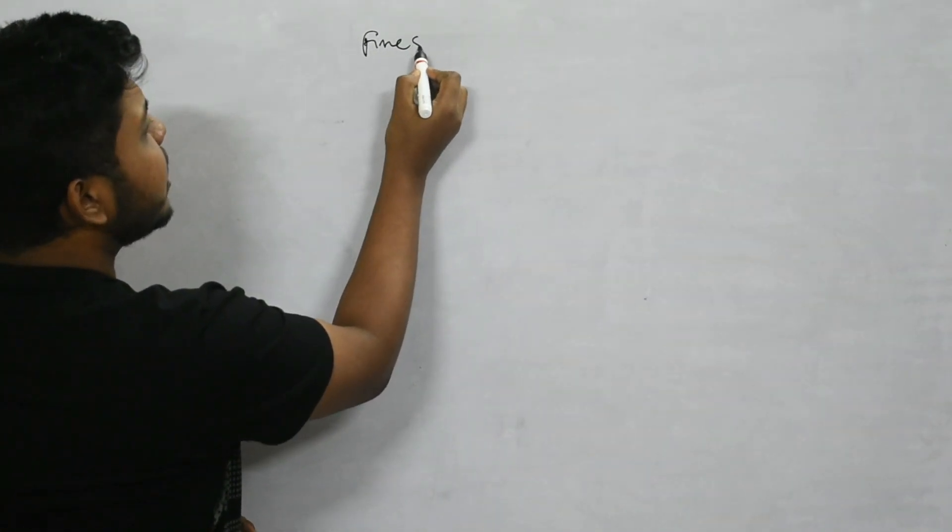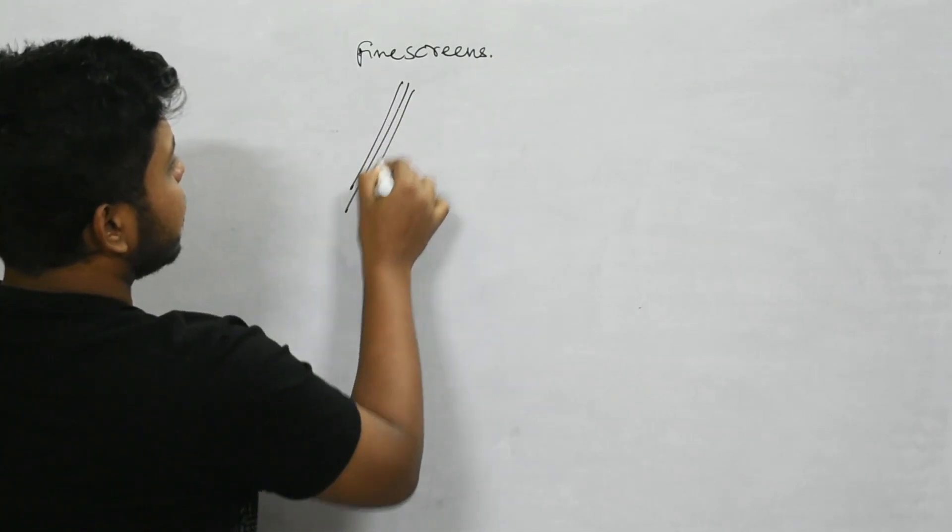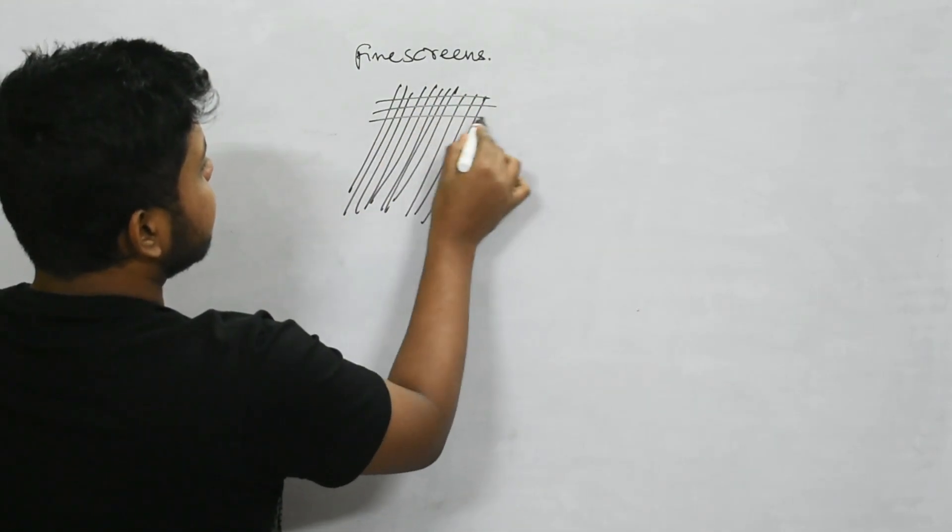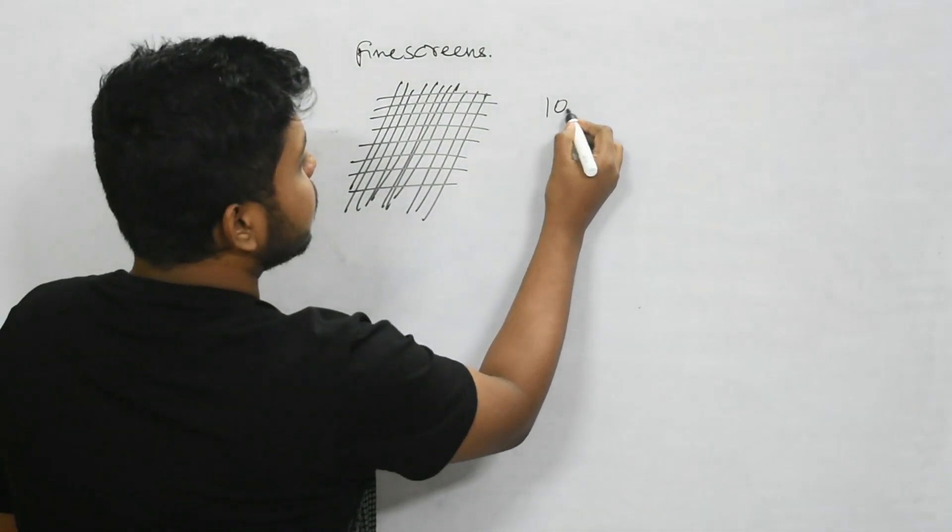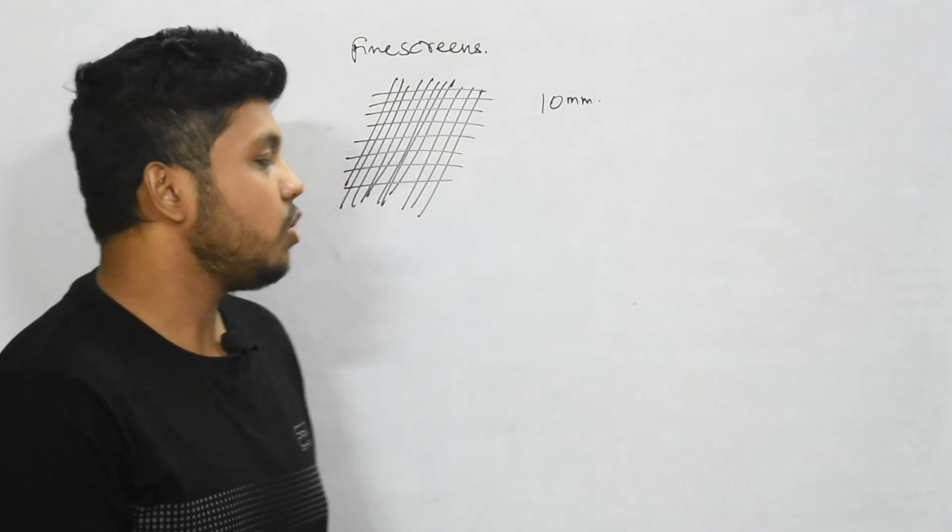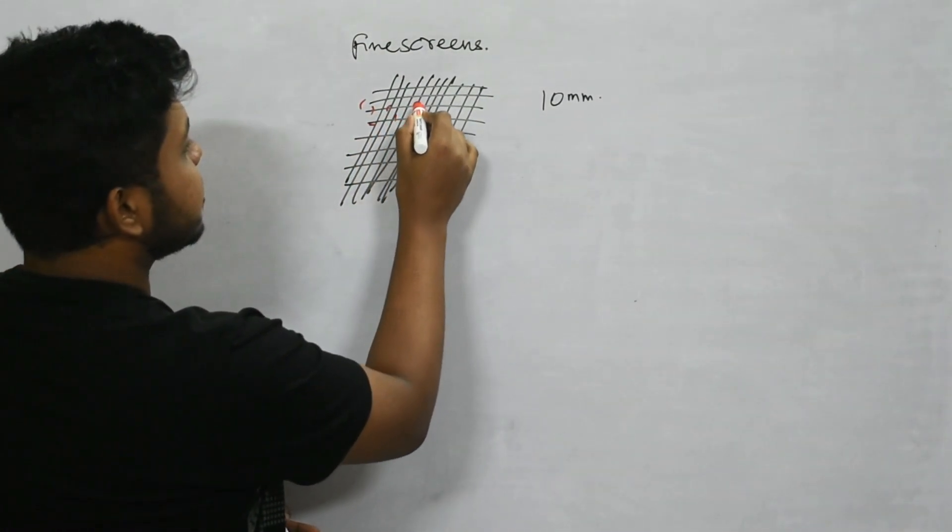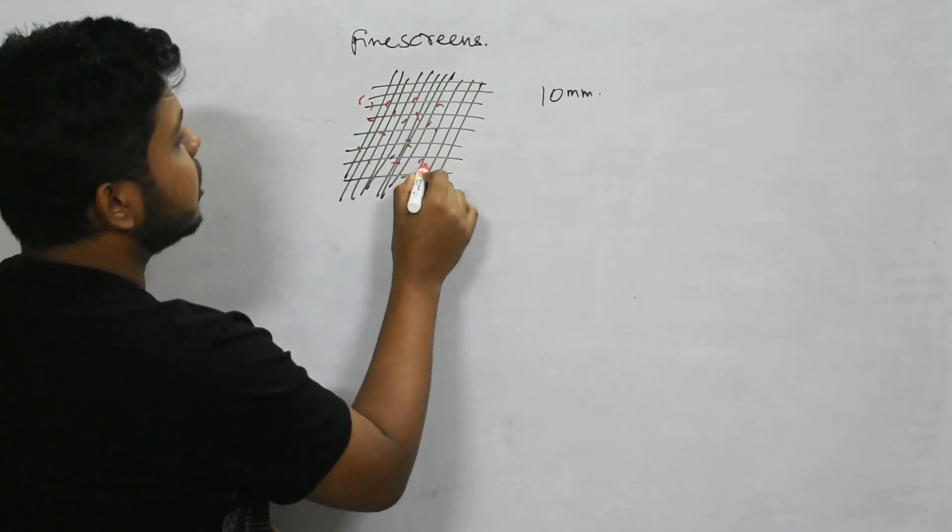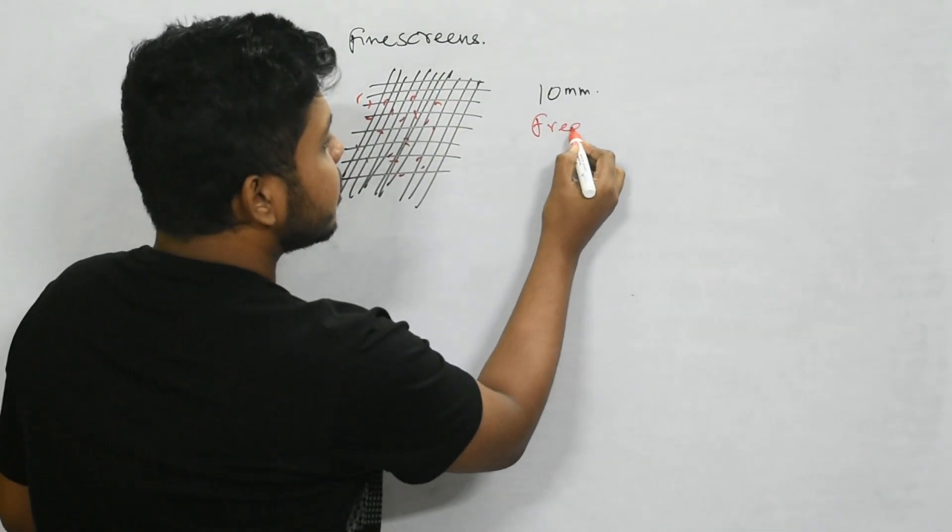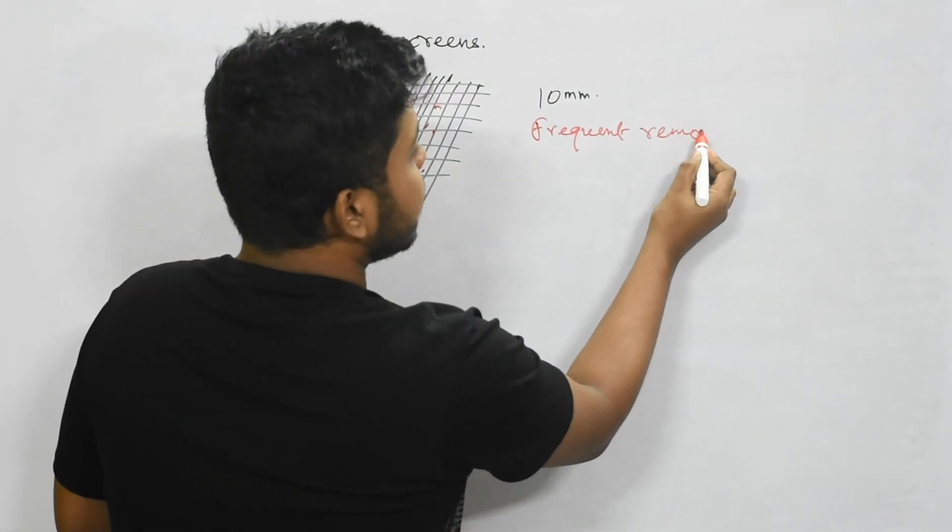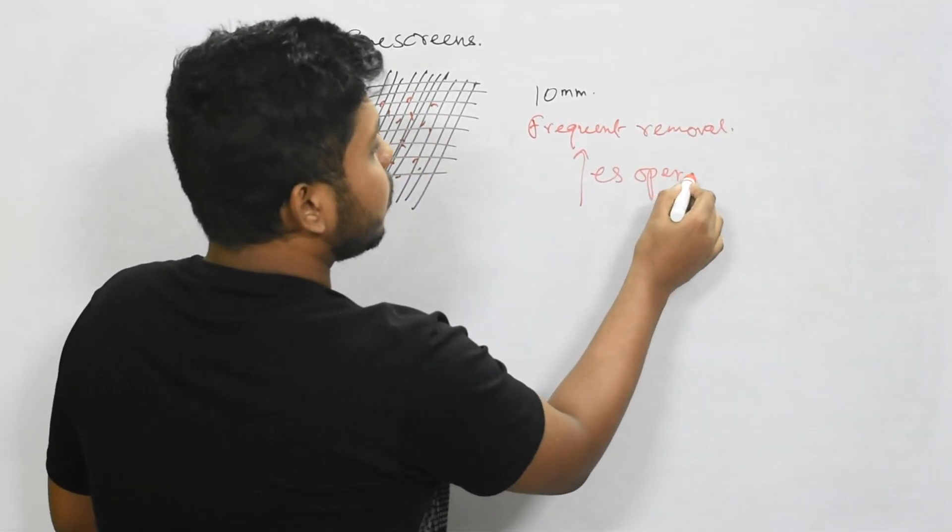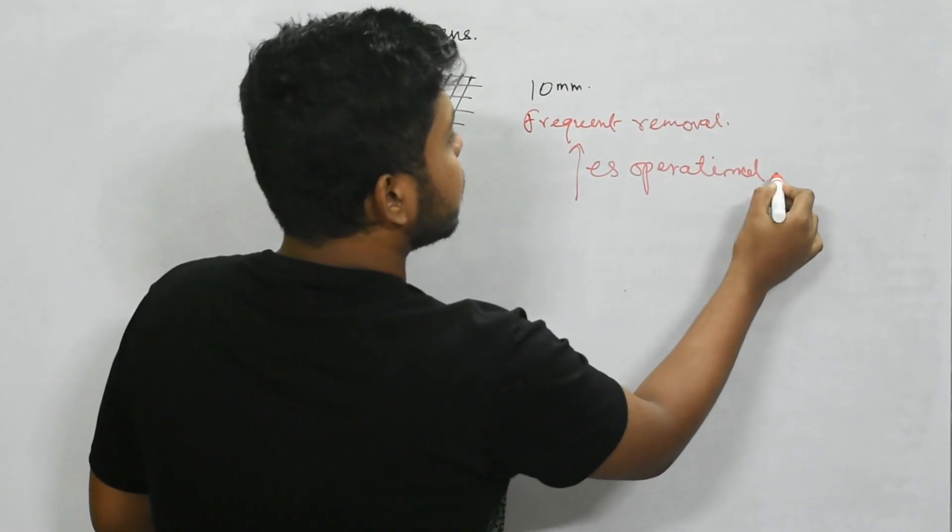Fine screens are wire mesh screens with very small openings of 10 mm or less. But these fine screens are avoided because the larger suspended particles get clogged very frequently which needs frequent removal. This frequent removal process increases the operational cost.